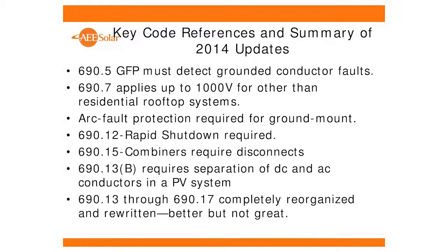2014 code, a lot more changes happened in that code cycle because it was the second code cycle with this panel. We have a requirement that our ground fault protector must detect grounded conductor faults, which was not specifically required in the past.